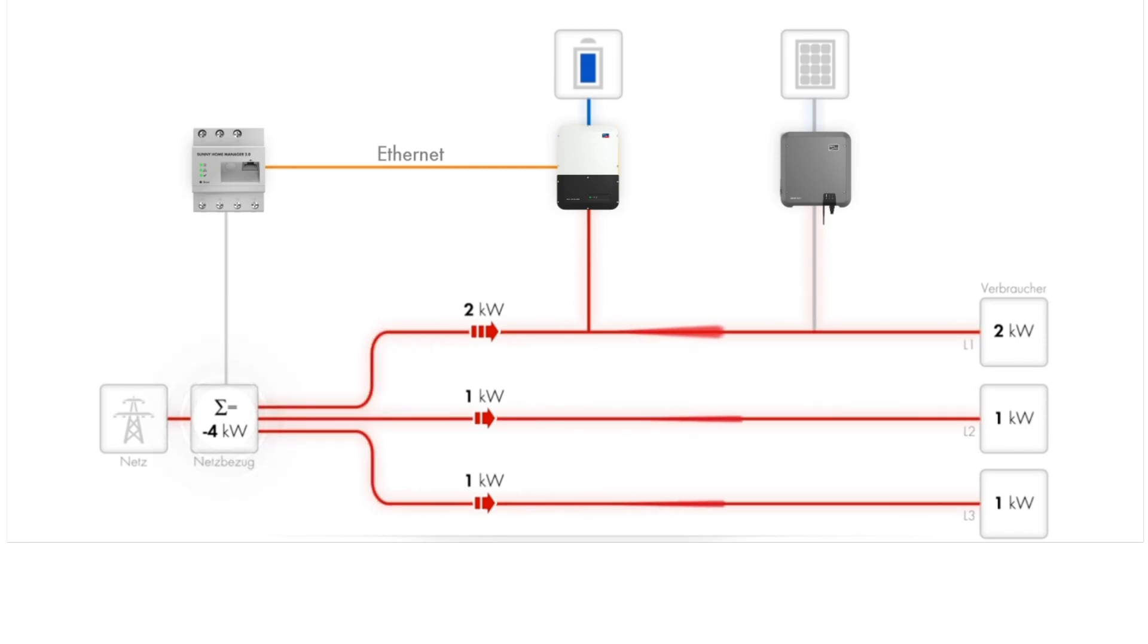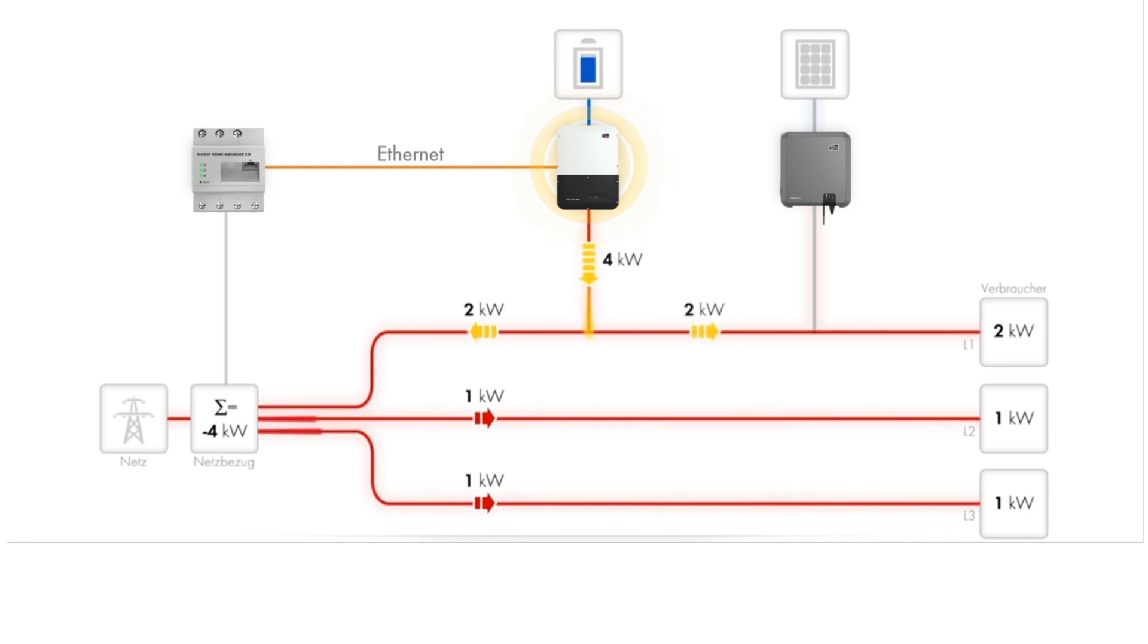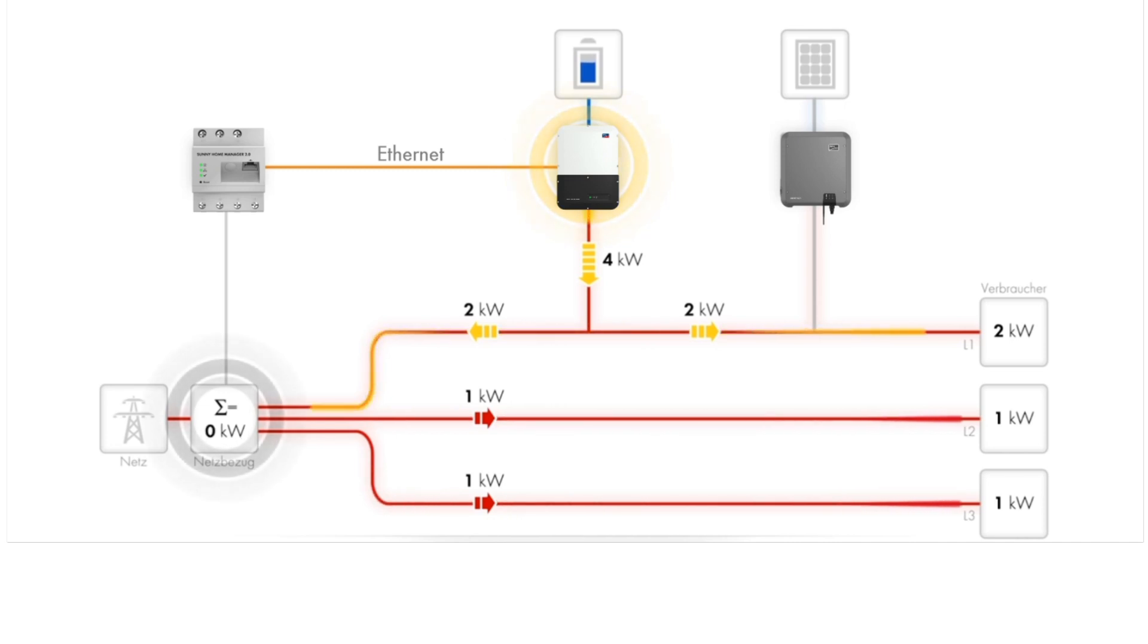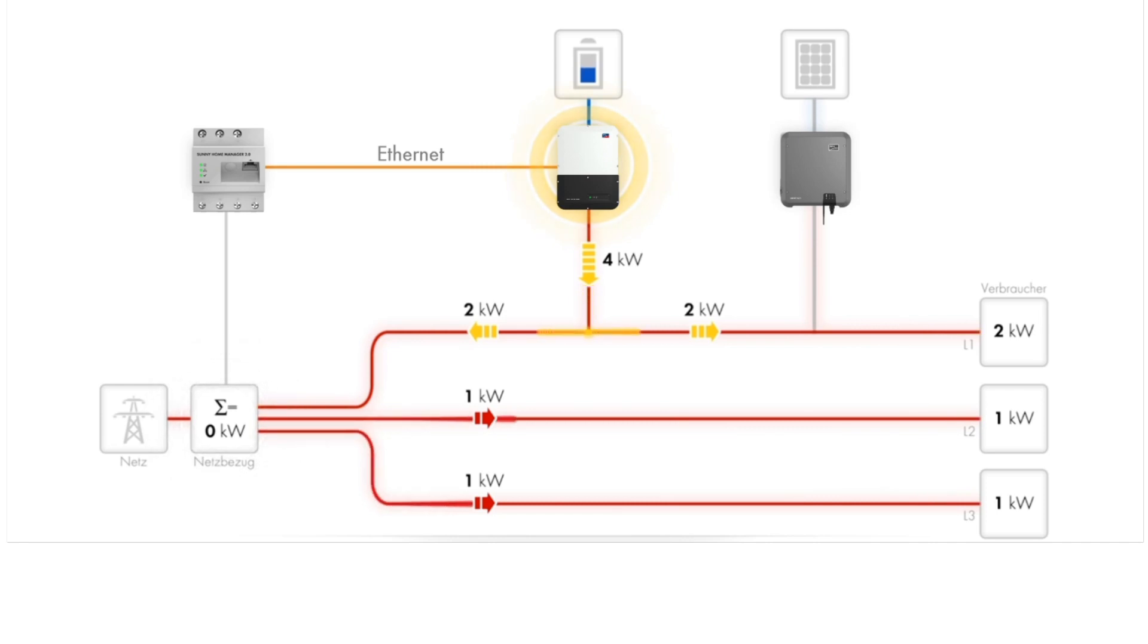In reaction to this, the Sunny Boy Storage and Sunny Home Manager will then discharge the battery at a rate of four kilowatts to compensate. Even though the load on line two and line three are not directly powered by the battery, the net energy flow across all three phases at the grid connection point is zero kilowatts.